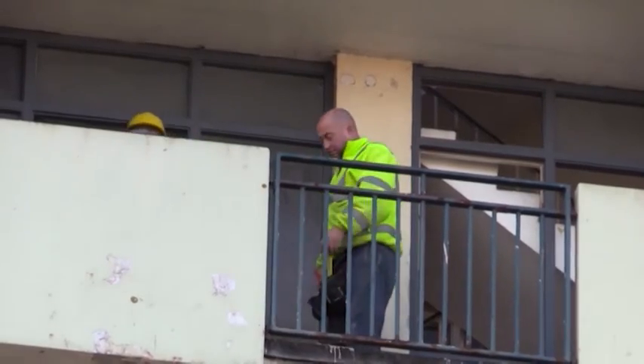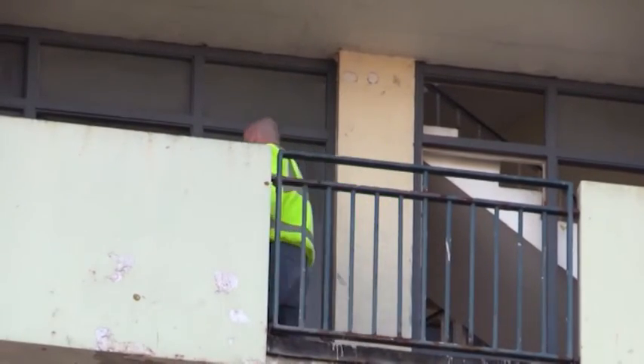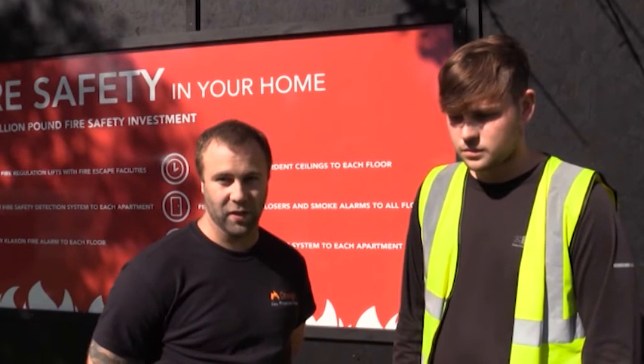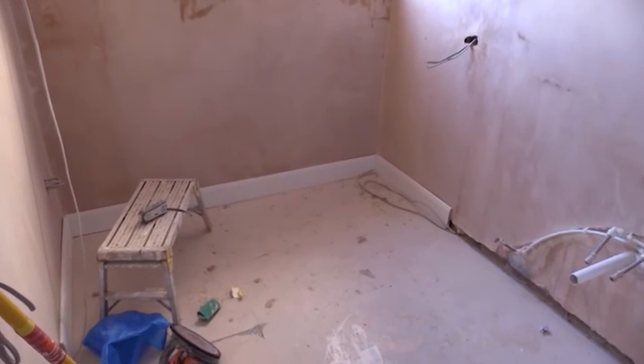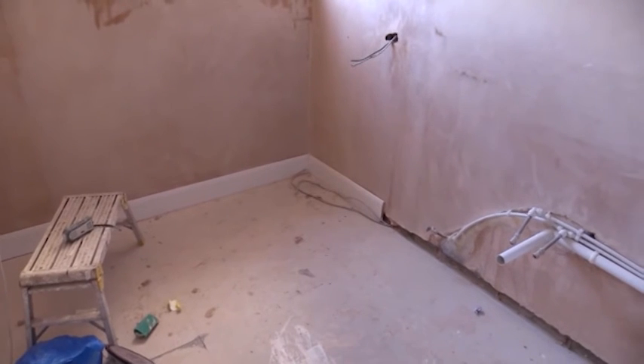There's also a riser running all the way through the building which feeds every single floor, with a valve on each floor to test the flow switches, triggering the fire alarm on the exact floor it's been set off. On the second fix, we then run around putting all the cover caps on the heads, which will drop off if the bulb ever pops, setting off the fire alarm as well as the sprinkler system.